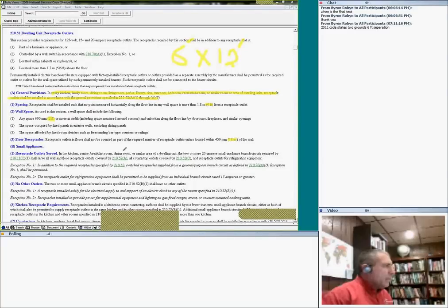Receptacles are always served in the kitchen. Then 20 amp circuit, guys. Remember, they have to be fed from a 20 amp circuit dedicated for the kitchen, and nothing else shall be connected to it. In addition, requirements, blah blah blah. Switch receptacles are supplied from a general purpose branch circuit.